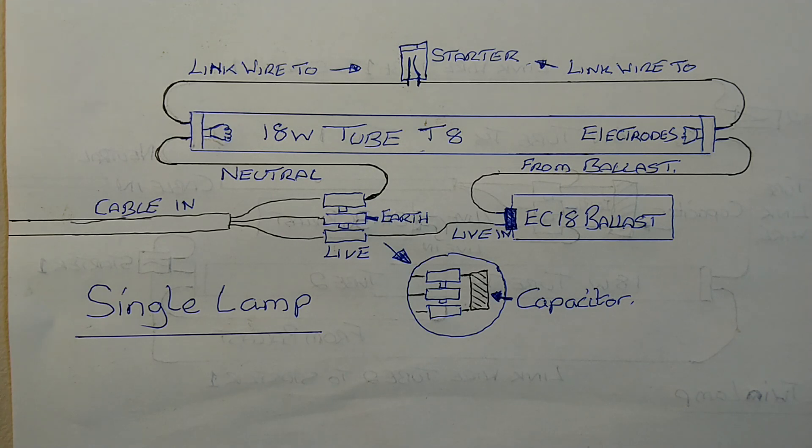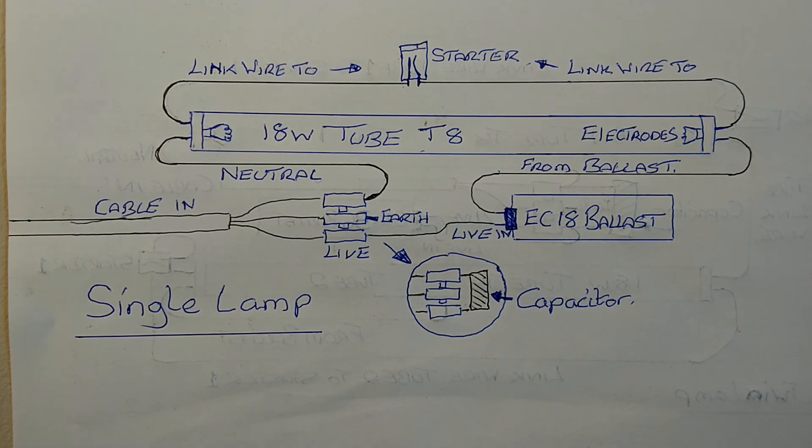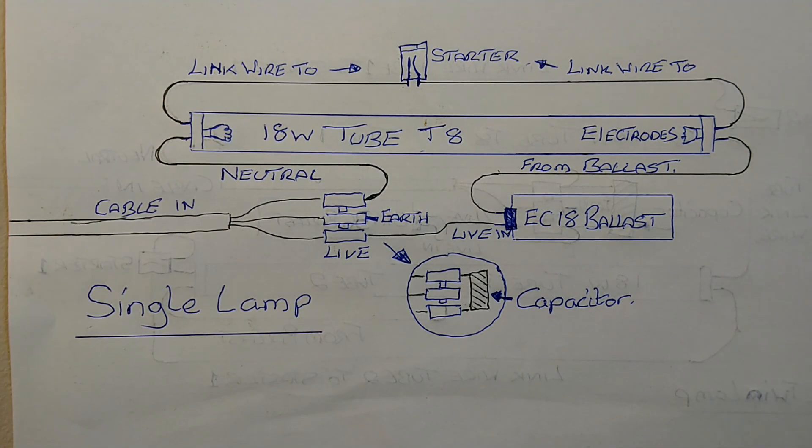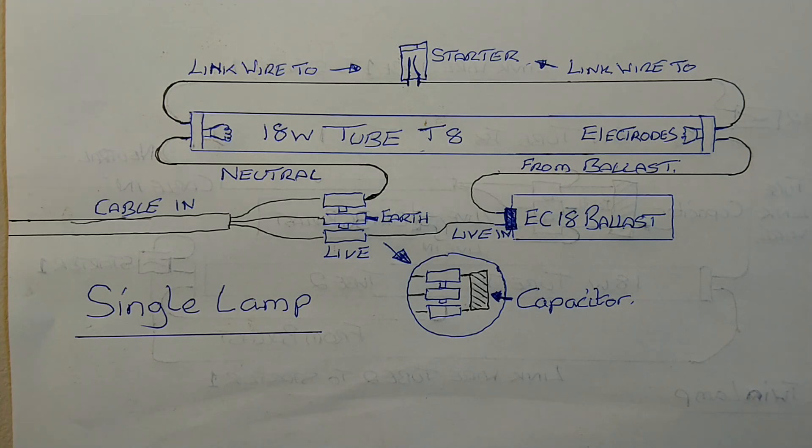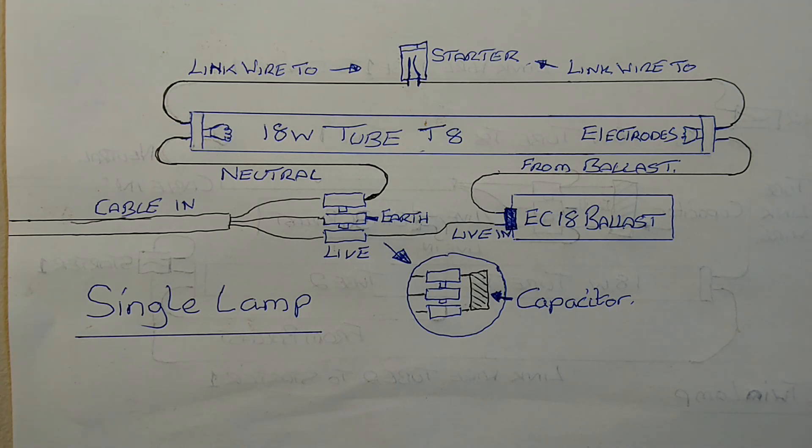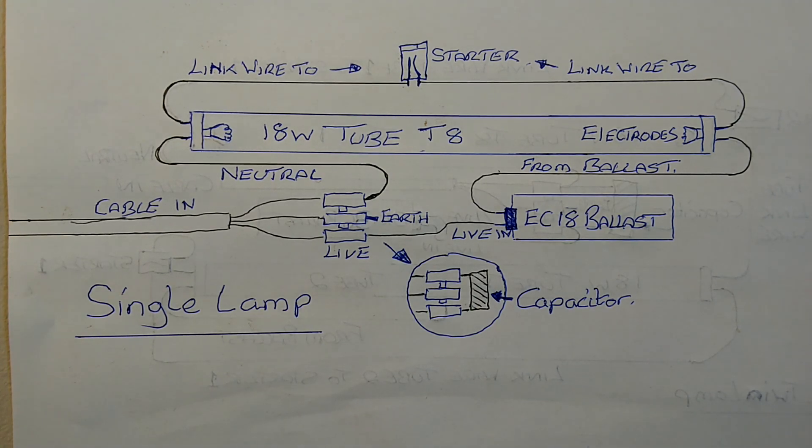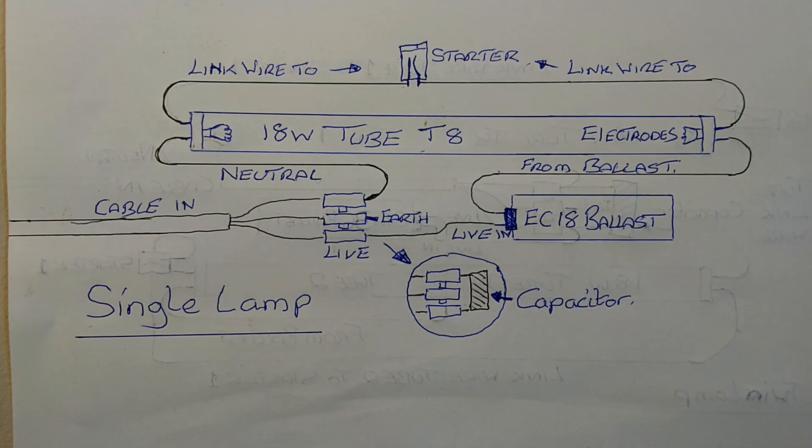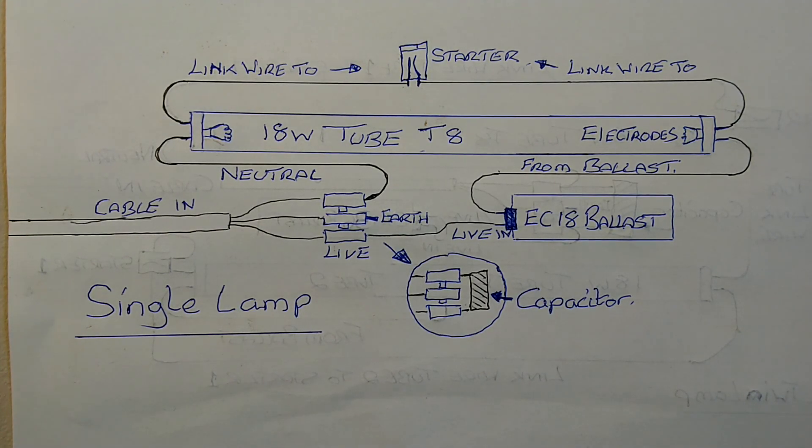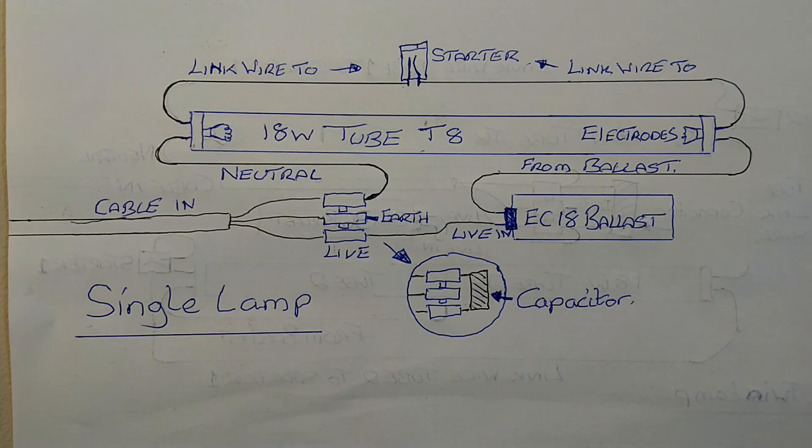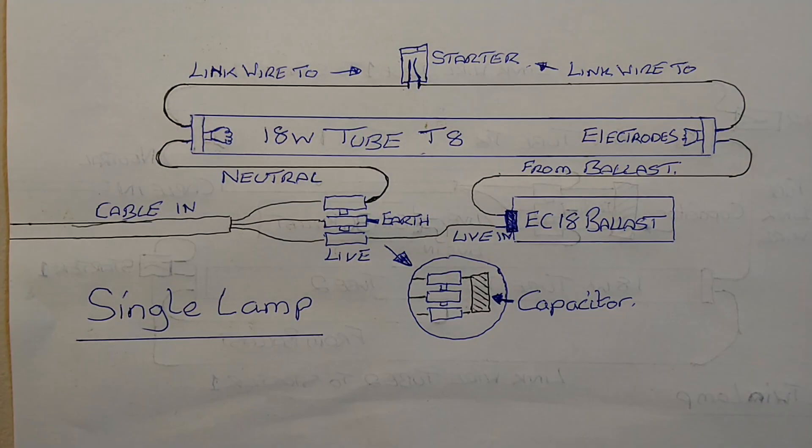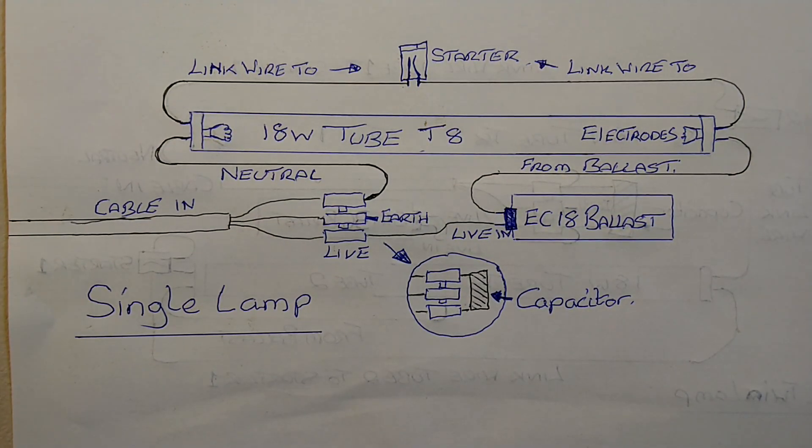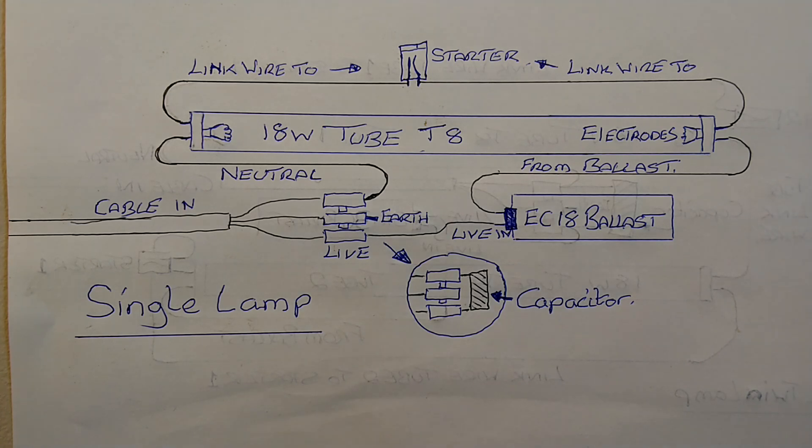When one of the electrodes goes bad, these lights will flash continuously until either the tube or the starter burn out. If the starter sticks for any particular reason, you'll get a tube that glows at either end. This is either a good tube which will probably have white ends glowing at either end, or if it's a dead tube it'll have like an orange end, probably at one end or both. So I think the best thing to do is now look at the light fitting a bit closer. But before we do that, I think we'll also show you the power meter and how this light is currently running. So I'll just move to the power meter.